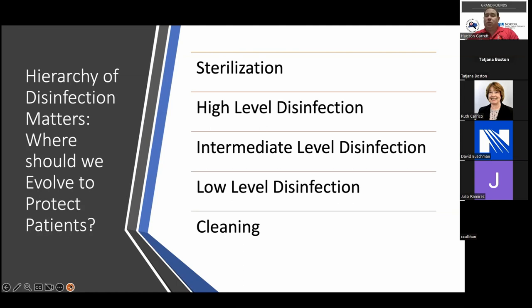Our semi-critical devices have a minimum of high-level disinfection, but there's no problem doing sterilization as long as it's validated by the manufacturer. That gives you a bit more wiggle room, removing that edge of patient safety risk.